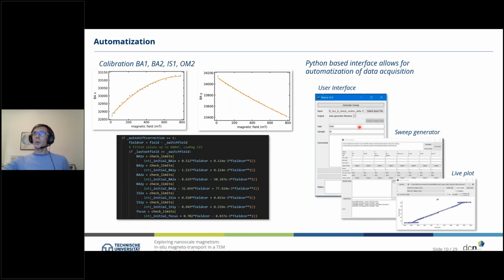But what is more important is the so-called sweep generator, which now combines our two different tools, the TEM on the one hand and the magneto-transport measurement devices on the other hand. There you define the magnetic field generated by the objective lens. You define the current which will run through your sample. You define the measurement points, the accuracy, the waiting times, and so on. And then running the experiment, we can see in a live plot how, for example, the voltage depends on the magnetic field of our sample.